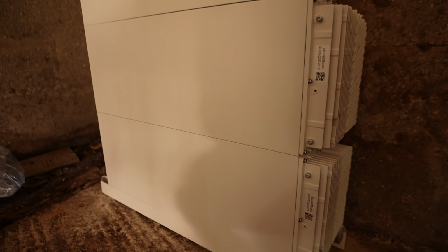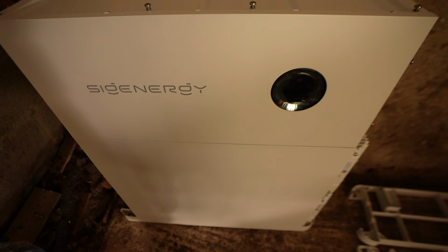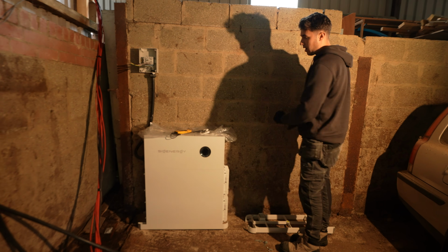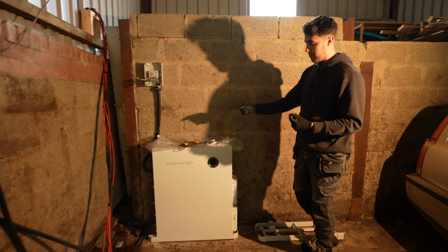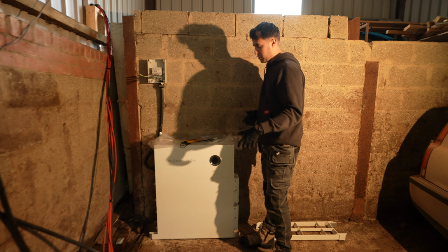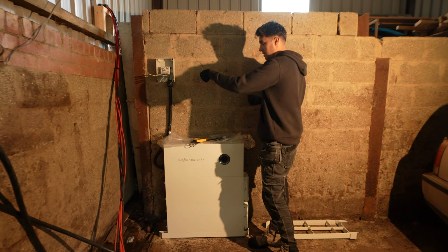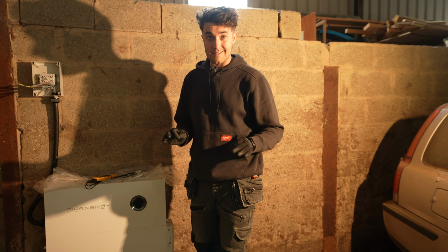We've got these two Sigenergy batteries and inverters. Basically each one of these stacks is an 8 kilowatt hour battery, and the inverter just sits on top. The plan will be to stack two to this height, with the idea that if we want to expand it in future, we just lift the inverter on, lift another battery stack on, and lift the inverter back on again. It's that simple, it's done.